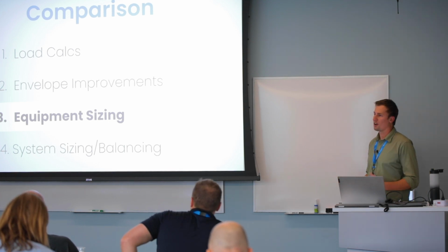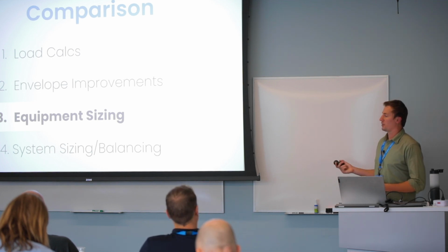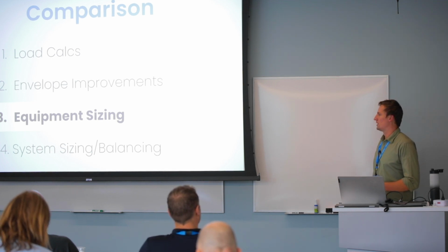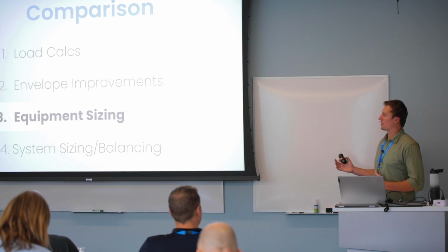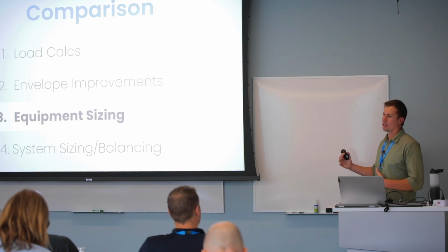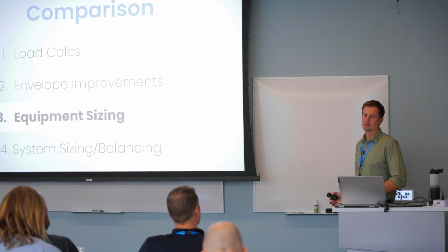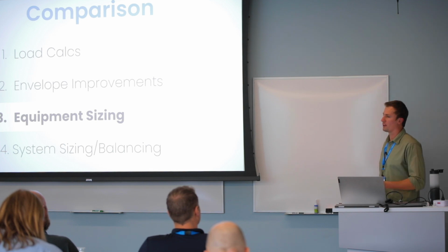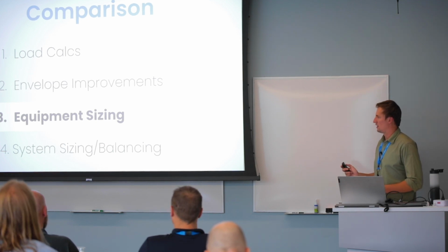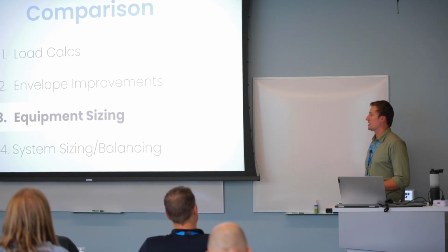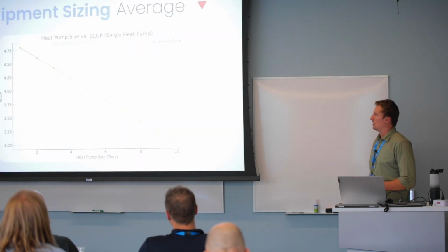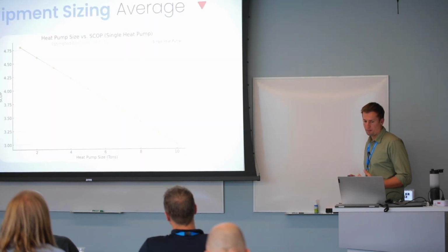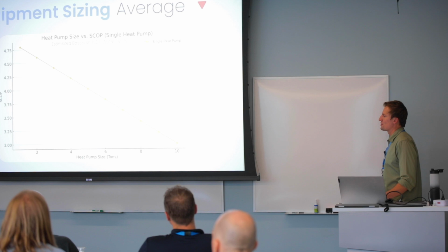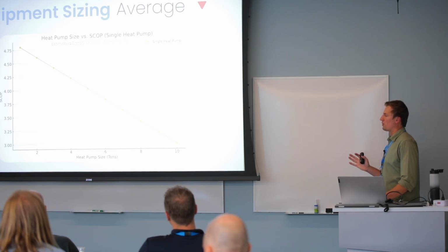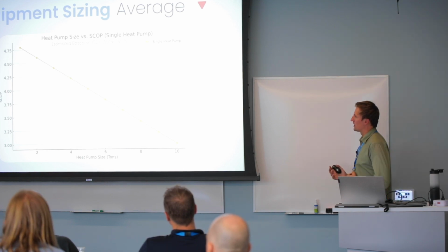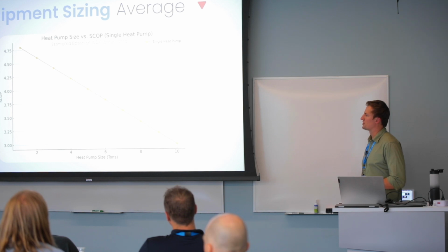Dissimilar to furnaces, where if you oversize, it's going to be okay. Not the case with heat pumps. Haven't really put any slides talking through that, but they're just designed to be on lower temperature, more usage, whereas gas furnaces, more just on and off, fast response times, which is why the oversizing doesn't work. And this is just for illustration purposes only. It's not based on any manufacturer specifically. It's just to show now how we choose the heat pump affects the coefficient of performance.